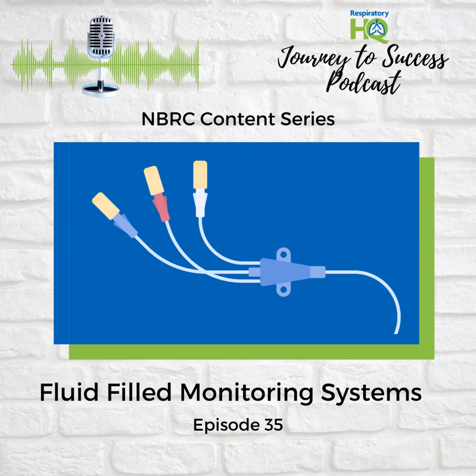And that's where another important step comes in. Zeroing the transducer. Okay, what is that? It's basically calibrating the system to make sure we're getting the true pressure reading. So like setting a scale to 0 before you weigh something. Exactly. We do it by aligning the transducer to the same vertical plane as the tip of the catheter, usually at the level of the patient's heart. That way, we eliminate the effects of atmospheric pressure, which can really skew the readings.